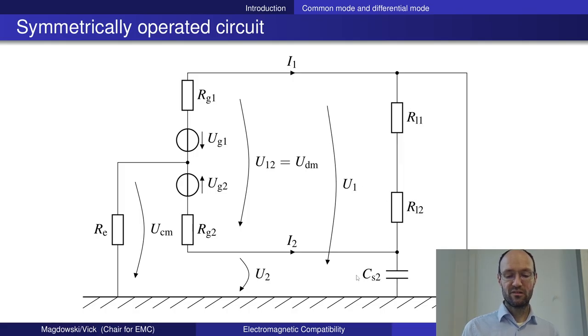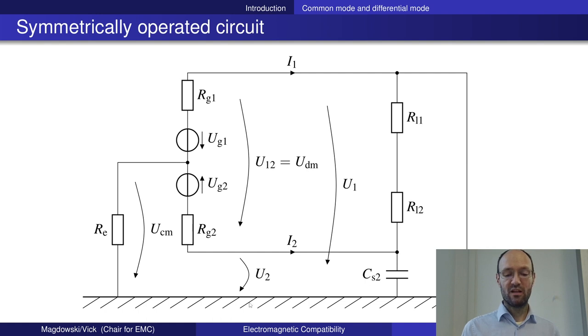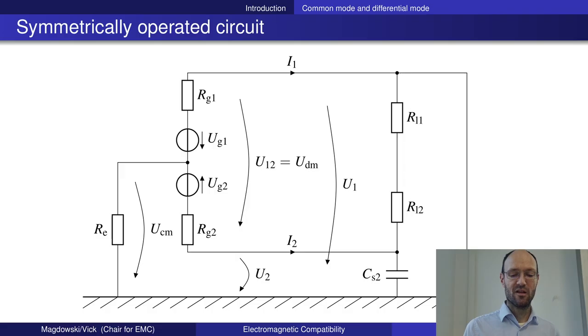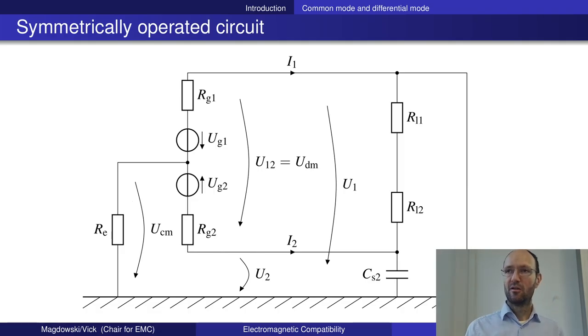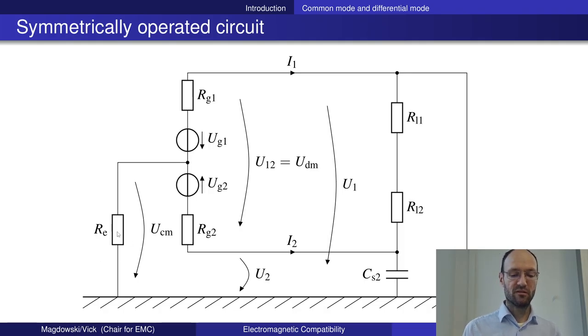Due to the stray capacitances, especially at higher frequencies, currents can also go over the stray capacitances and then return somewhere else — for example on the ground plane, on the chassis, on the case of some system. So you have currents going strange ways, for example also on pipes of the heating system of a building, and returning via some grounding impedance or maybe via other stray capacitance instances back to the source.